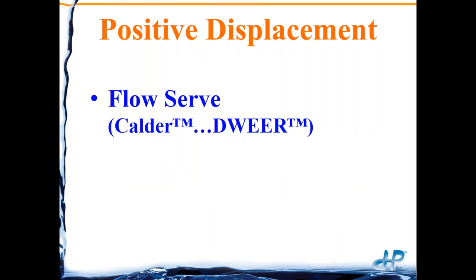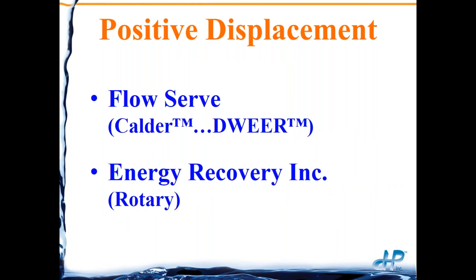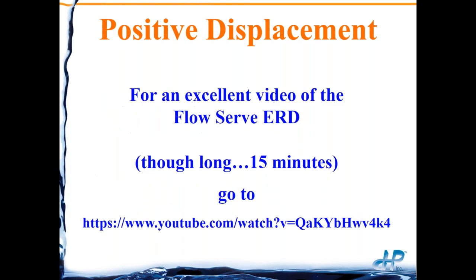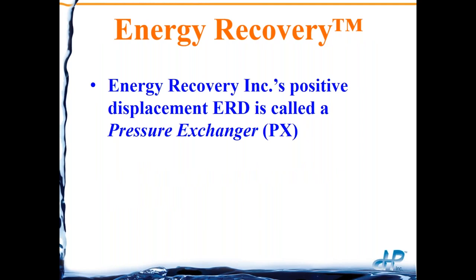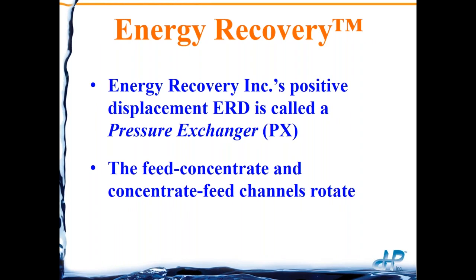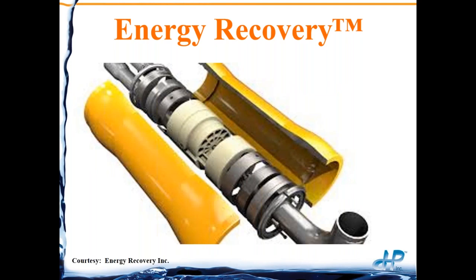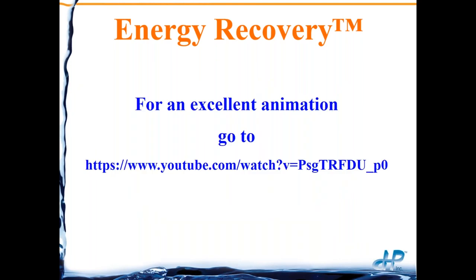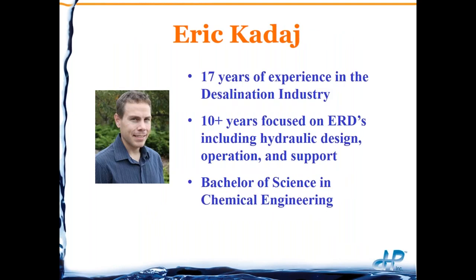For positive displacement, the piston system I just showed is the FlowServe, also known as the Calder or Dweer system. Energy Recovery has a similar concept but quite different — if you want to see a video of the FlowServe ERD, there's a YouTube address you can go to. I'm not going to go into detail on Energy Recovery's device — I'll just introduce it because Eric is going to take over. They have a positive displacement device called a pressure exchanger, and one of its unique features is that the channels are rotating, not going back and forth, and there are no pistons.